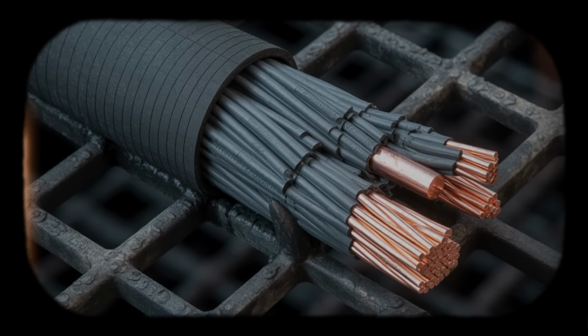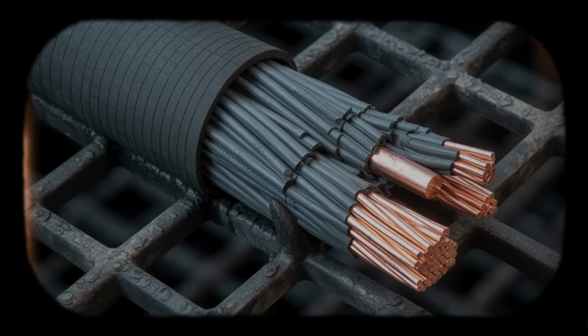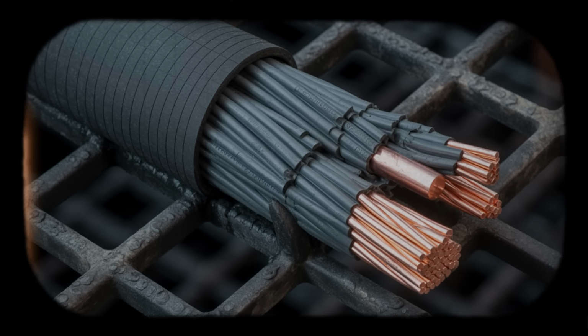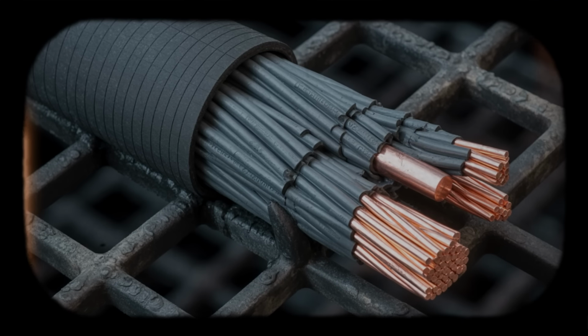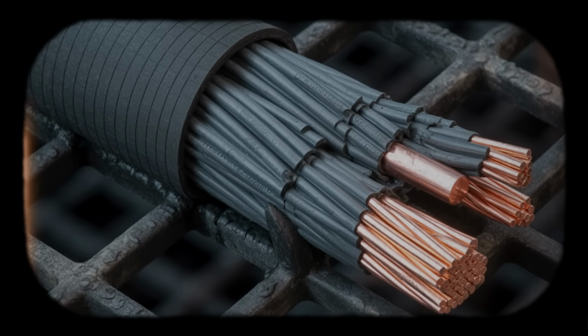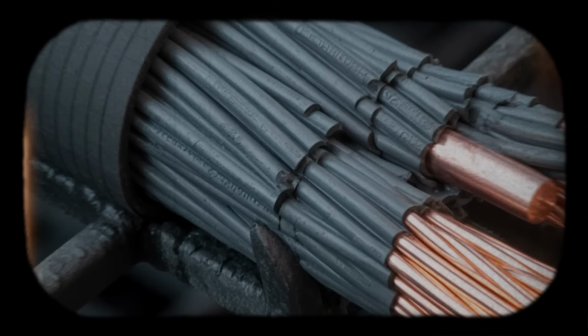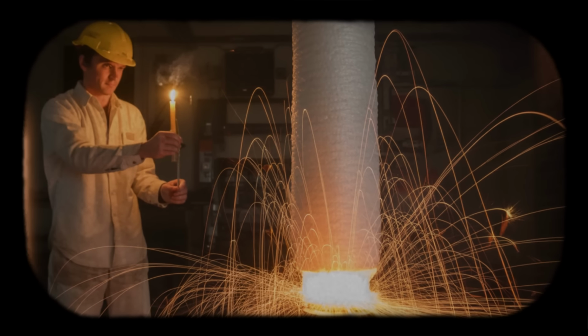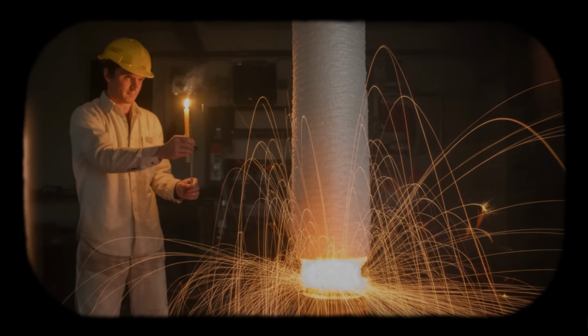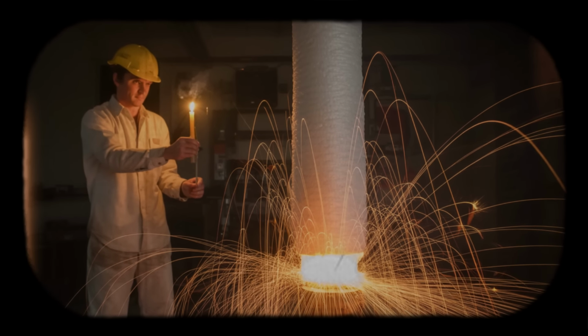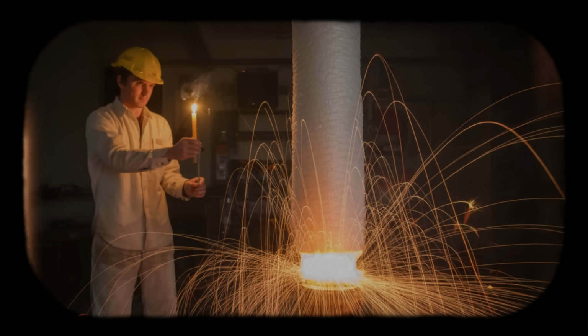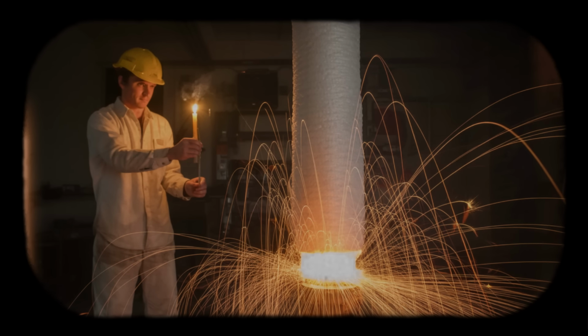Water fog, a fine mist rather than a solid stream, offers a compromise. It cools burning material more effectively than CO2. It penetrates cable bundles more thoroughly. The fine droplets reduce but do not eliminate electrical hazards compared to solid streams. Emergency ventilation fans are brought in to clear smoke, improving visibility and allowing firefighters to reach deeper sections of cable trays. The decision to use water introduces new risks.